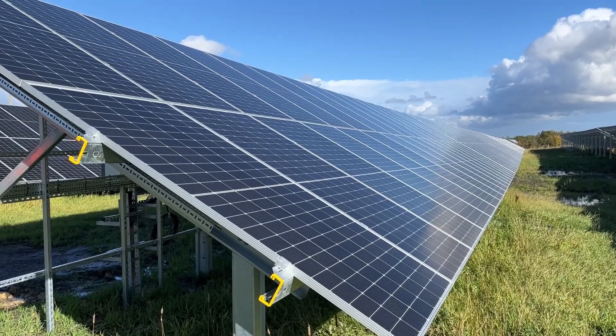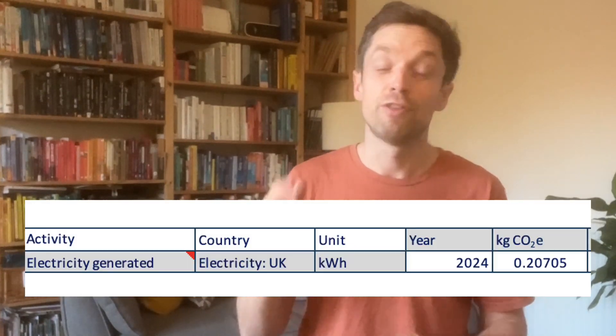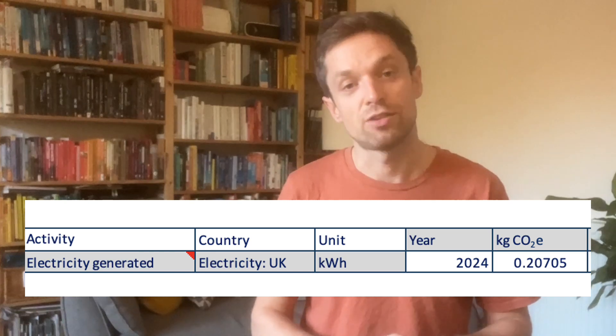We're using a little bit of electricity to move heat from outside to the inside. Next up: emissions. A heat pump still has some CO2 emissions associated with the electricity used to power it, but because of high efficiency it's using much less energy to heat a space. And because the grid is getting cleaner and cleaner, a heat pump will get cleaner too. Best practice is to use the UK average grid emissions, which for this year are 207 grams of CO2 per kilowatt hour of electricity. So our emissions over the whole year for heating were around 883 kilograms of CO2.